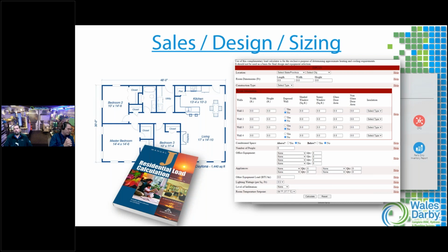Yeah, even when you use these programs, you're a little oversized because they do have a little bit of a fudge built into them. So usually if you do the math and follow the numbers right to the number, there's still a little bit of a percentage there. I don't know what each program uses, if there is a standard. The number I heard was like 30%. 30%, okay. I heard 15, so 15 to 30%. So if you follow the numbers that you see on the screen, it's going to be even a little oversized, if anything, at that point.